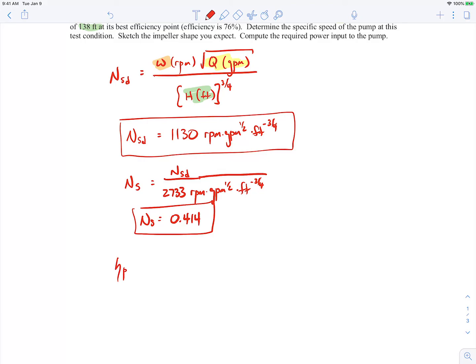I'll start with the efficiency of the pump since that was given. The efficiency of the pump is the power that goes into the fluid divided by the power that goes into the pump. Keep in mind that all of the power that goes into the pump doesn't make it into the fluid. There's some inefficiency. Some power goes into bearing losses. Some come into fluid mechanic tip losses like flow sneaking around the impeller tip. It doesn't really contribute to the head rise in the fluid.